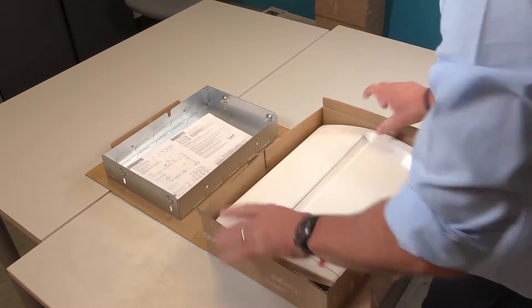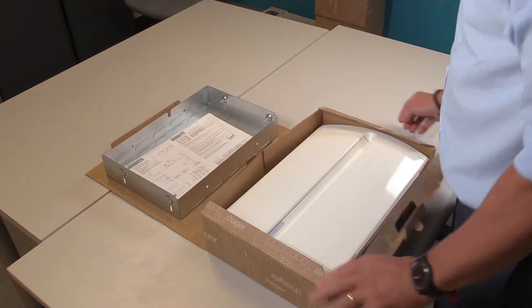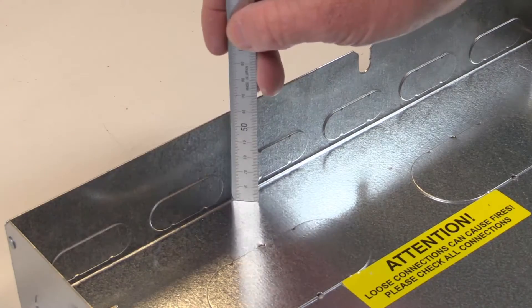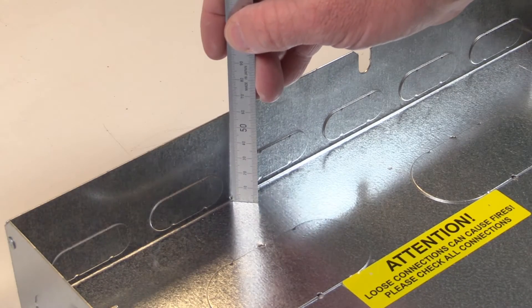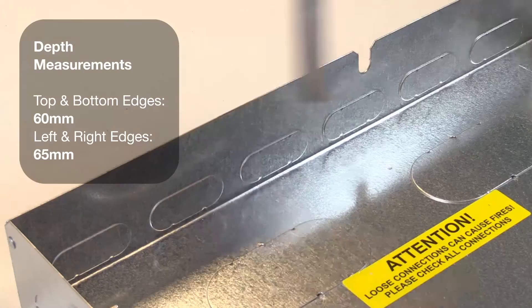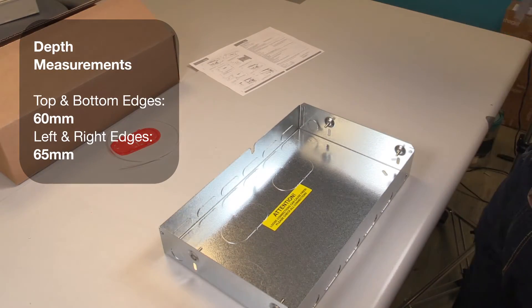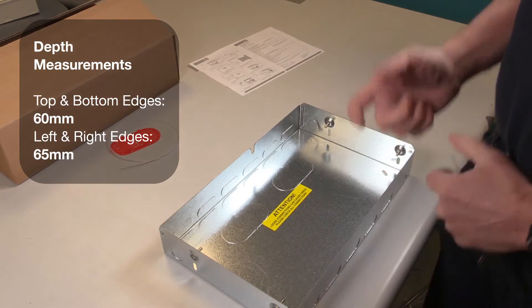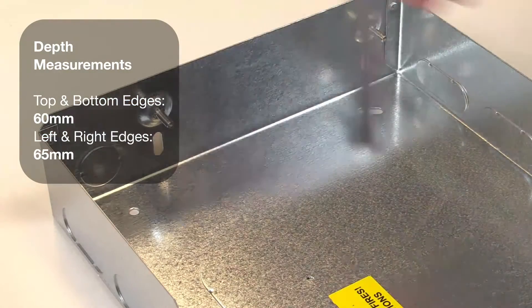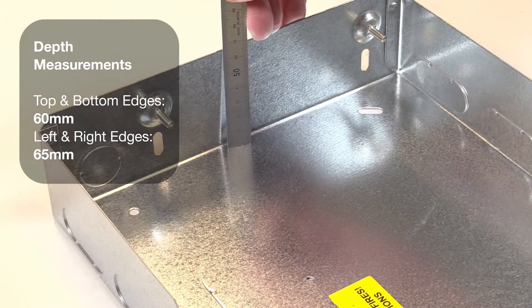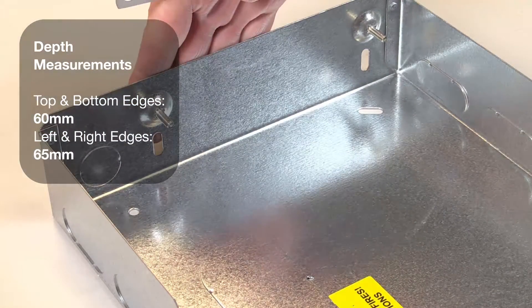Before installing a flush consumer unit, we need to understand how deep into the wall the back box needs to be. The top and bottom edges are 60 millimeters deep and need to be no further forward than flush with the stud work. The side edges are 65 millimeters deep. These raised edges allow you to have an edge to work up to with the plasterboard.